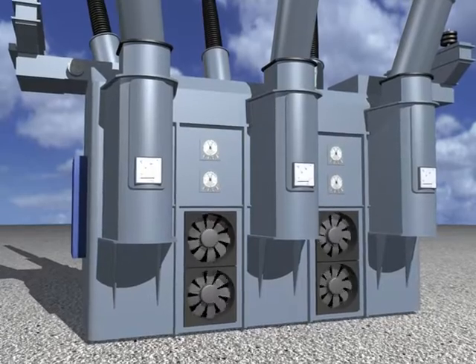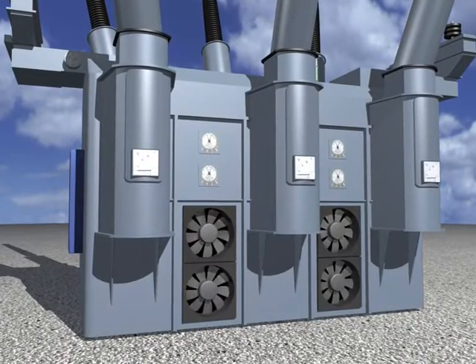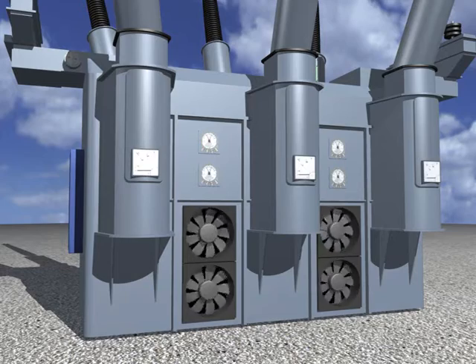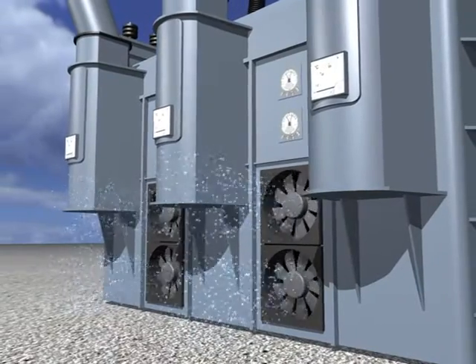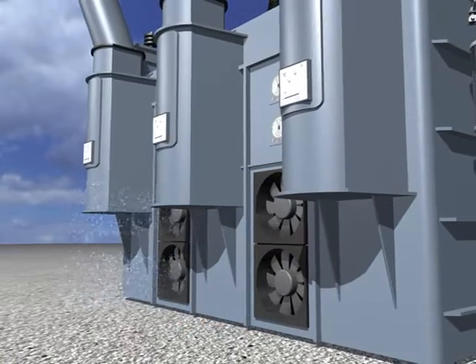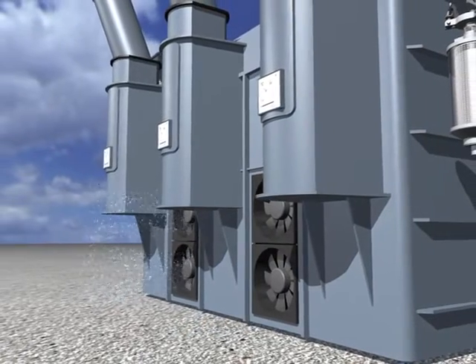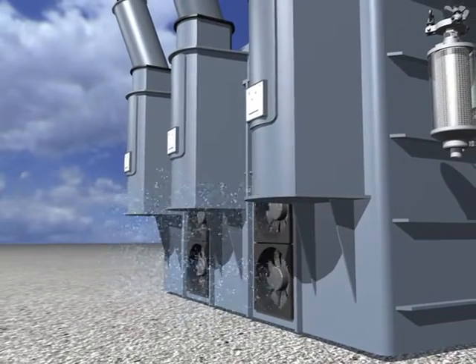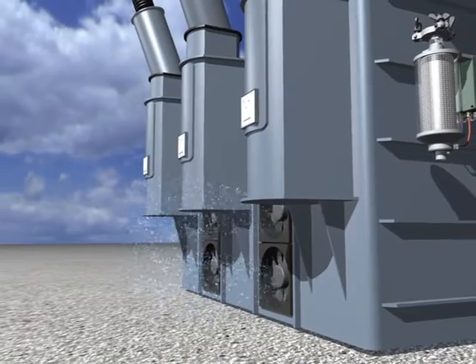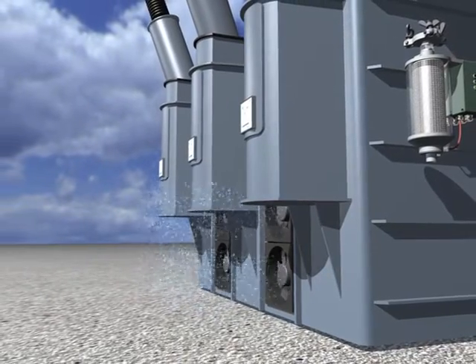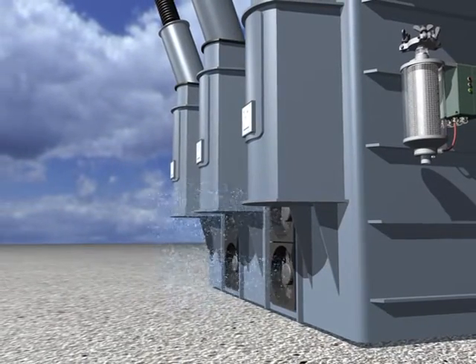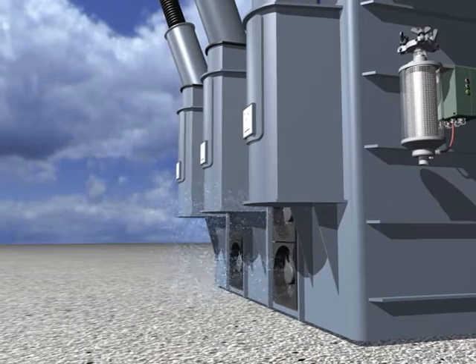The load-dependent temperature monitoring of the MTeC system controls transformer temperatures within the required limits and simultaneously reduces fan and pump operation to an absolute minimum. The additional load change circuit ensures that the individual fans are equally loaded. All temperature and fan control is based on proven algorithms from the IEC and ANSI standards.